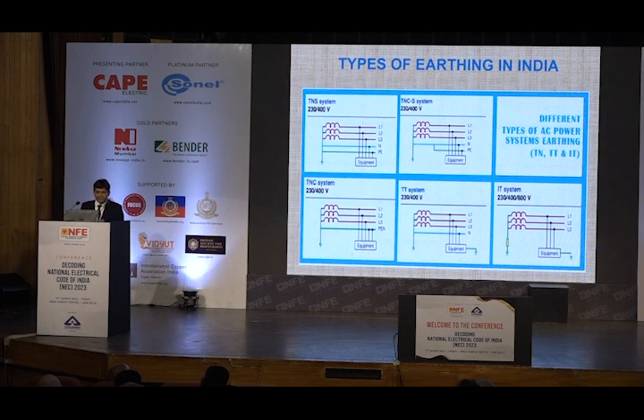Now, for the distribution systems, we have these 5 types of earthing systems available. One is your TN-S system, then TN-C-S, TN-C, TT, and IT. T means terra, that means earth, and for neutral, S for separate, C for common. I for isolated. And every system has its own significance.